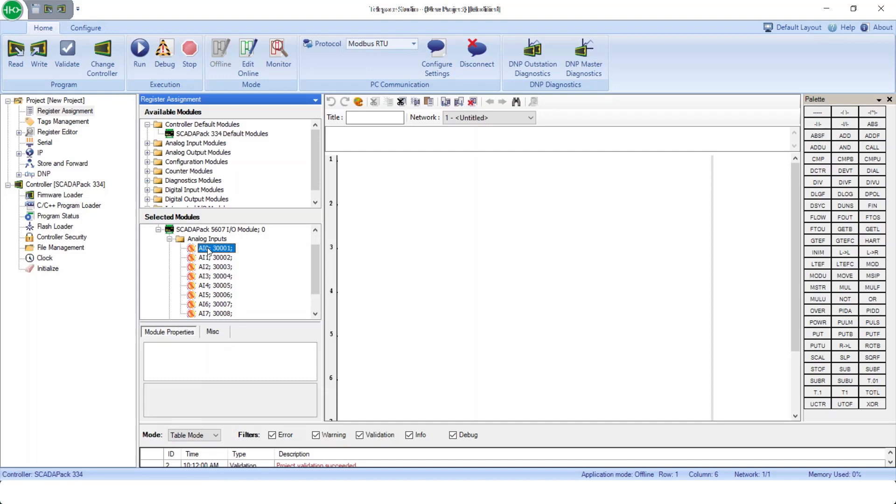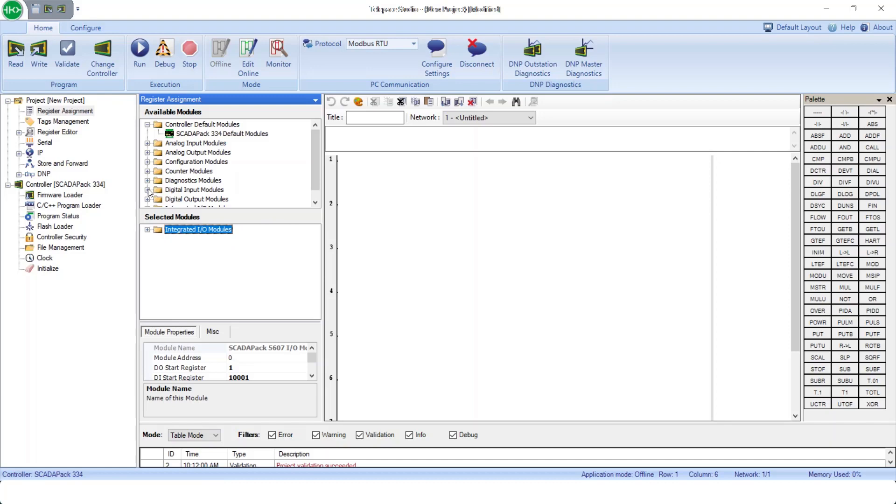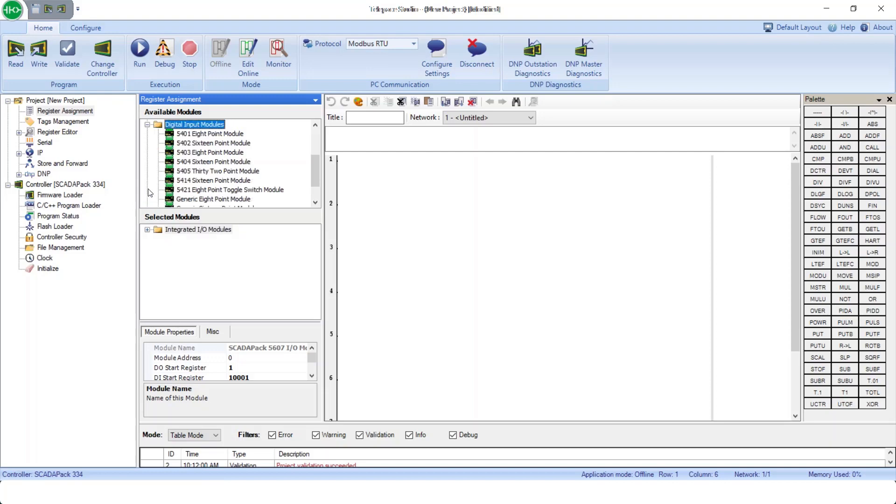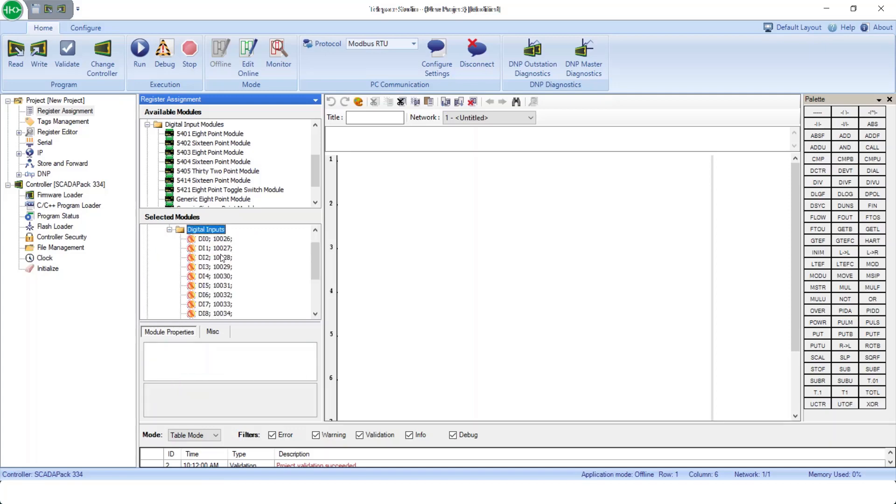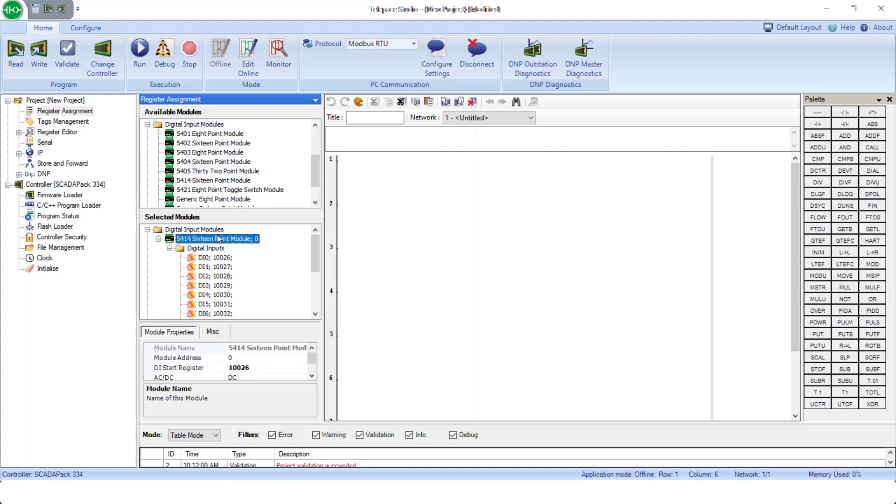Note that all data points in the standard SCADA pack must be tied to Modbus registers, which is somewhat limiting. We can add expansion I/O modules if needed. For example, in the Digital Input section, we could add a 5414 16-point digital input module. And note that again, each digital input is tied to a Modbus point. These default registers can be modified if desired.